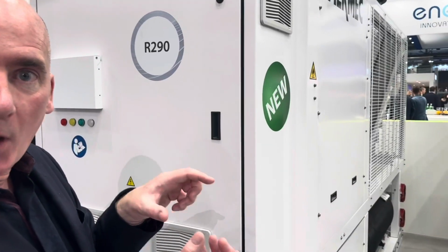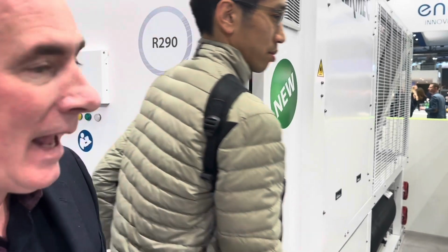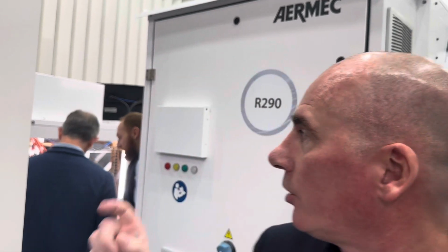The beauty about the PRN is, because they're a modular unit, you can basically stack them together. They come with two pipe sections, as you can see at the back, which are basically 1 meter apart. So you can basically stack them 1 meter apart and up to 9 units together. So basically 900 kilowatts. So it's essentially a 900 kilowatt chiller. There is another unit here, the PRG, that goes with about 150 kilowatts. Again, we're limited on the capacity that they can make these because the more volume you have, the more minimum technical space you're going to need. So consequently, we're going to find we have more smaller units, and also I think we have 2 refrigerant circuits in all of these as well.